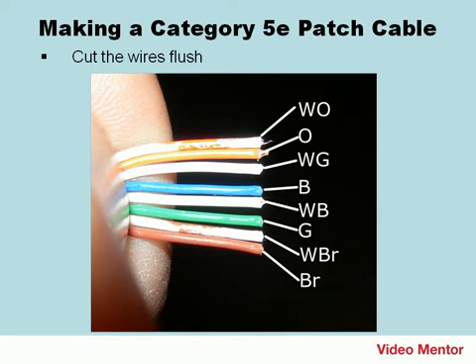You'll need about half an inch of wire exposed after the cut is made. Really, the wire isn't exposed — it's the wire with its plastic coating. But as far as the plastic jacket goes, you want a half inch of these wires exposed. Keep your thumb on the wires after the cut is made to keep them in place. The order should be: white-orange, orange, white-green, blue, white-blue, green, white-brown, brown.